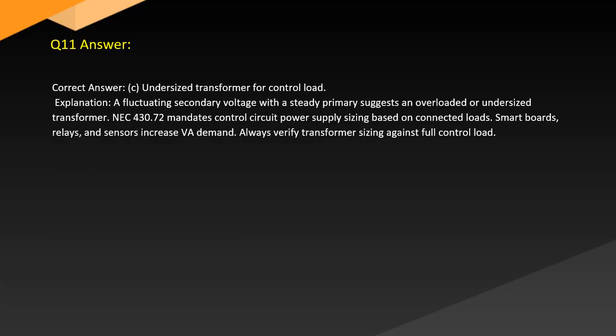Answer. Correct answer: C. Undersized transformer for control load. Explanation: a fluctuating secondary voltage with a steady primary suggests an overloaded or undersized transformer. NEC 430.72 mandates control circuit power supply sizing based on connected loads. Smart boards, relays, and sensors increase VA demand. Always verify transformer sizing against full control load.